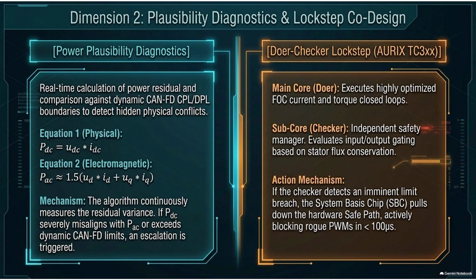If the power exceeds the safety limit by 15% or more for just 5 milliseconds, the system determines that software control is either lost or totally insufficient. Wow, 5 milliseconds is nothing. Right.